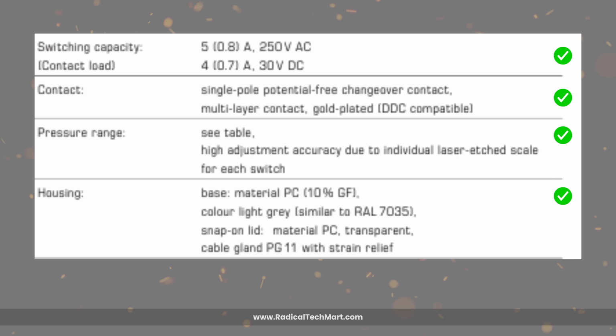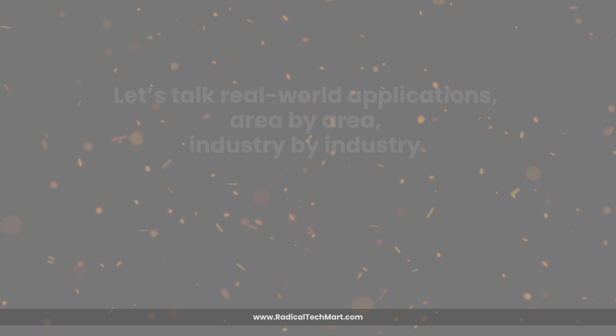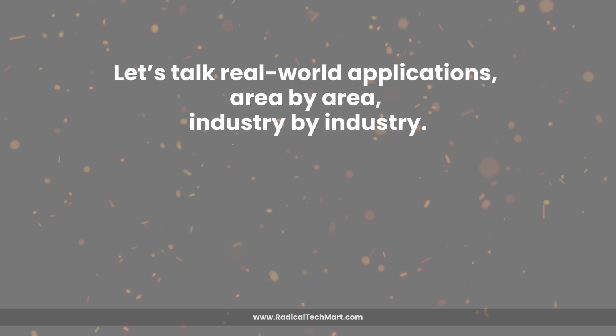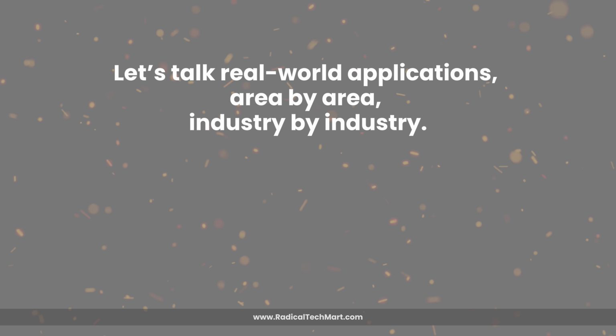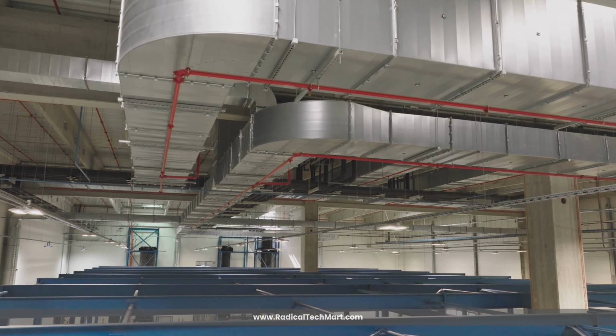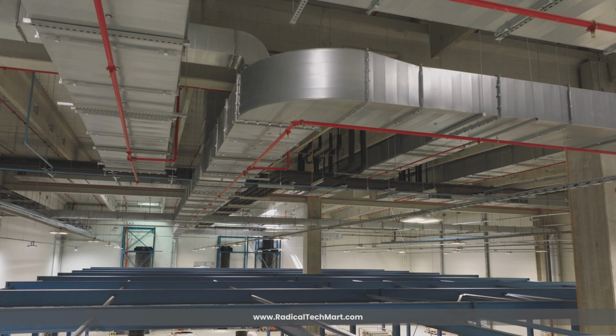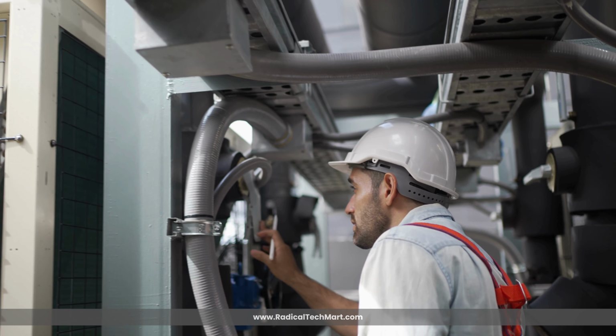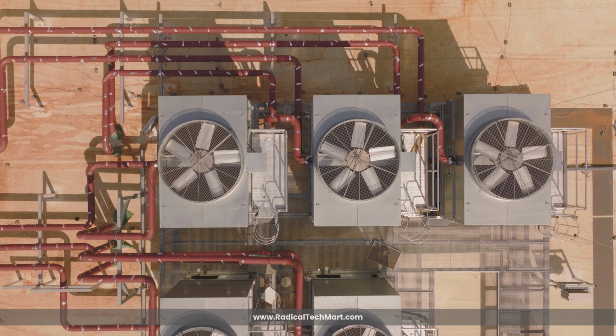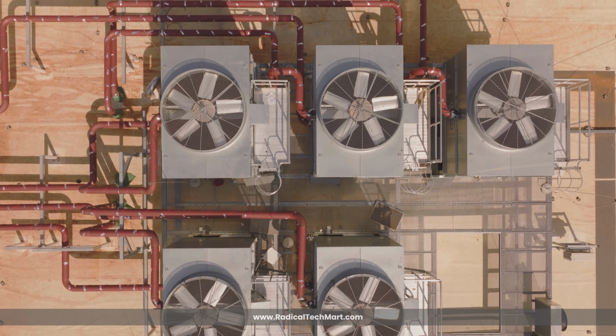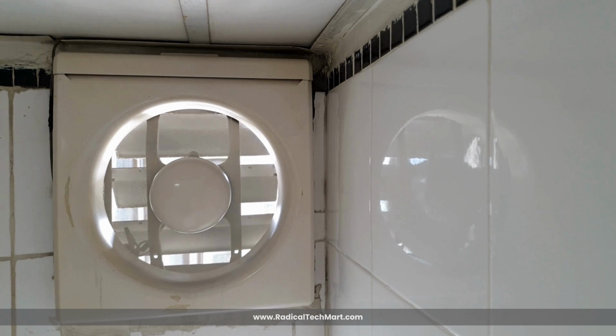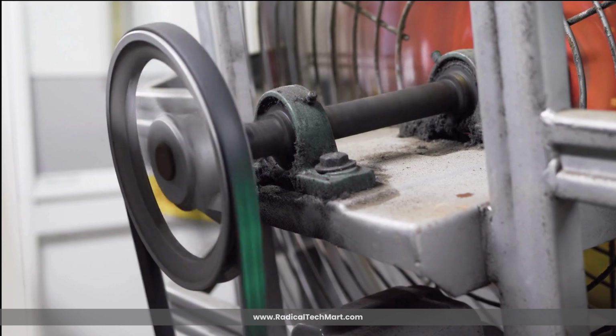Now, where exactly do these switches shine? Let's talk real-world applications, area by area, industry by industry. 1. In HVAC and building automation, the switches can be used to monitor clogged filters in large air handling units, ensure airflow before electric heaters activate, detect pressure drops across fans or ducts, and trigger alarms if belt-driven fans malfunction.